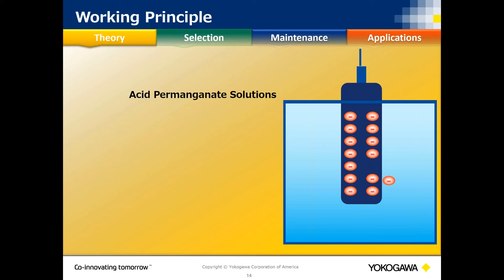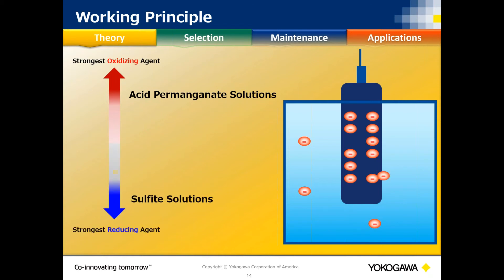Looking at the working principle on a noble metal with a reference system: a strongly oxidizing acid permanganate solution strongly attracts electrons from the noble metal electrode, generating a highly positive millivolt value. The opposite — a sulfite reaction — is strongly reducing, pushing electrons into the metal and generating a strongly negative millivolt value.